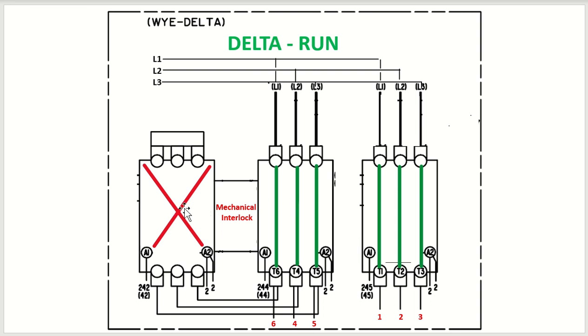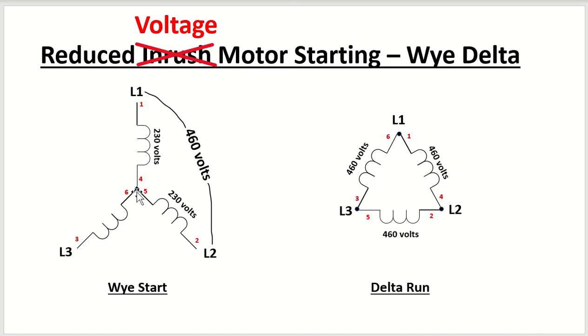Of course, you never would want these two contactors to pull in at the same time, the shorting contactor and the run contactor, because if they did, you would have a dead short, blow the fuses. So there's a mechanical interlock here, and that means that there's going to be a certain period of time between when you start pulling this contactor, close your shorting contactor to do your Y configuration. There's going to be a short period of time when you have to stop and restart the motor, and that's called the transition period, and I'll talk a little bit more about that. But once you transition from the Y configuration to the delta configuration, whether it's based on amperage or based on time, the motor comes up to full voltage.